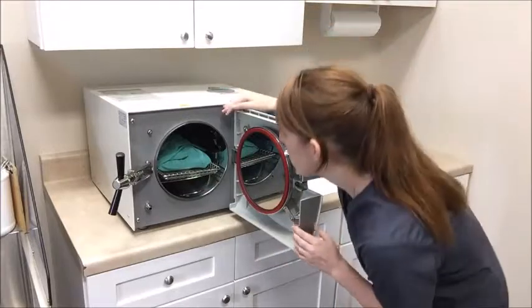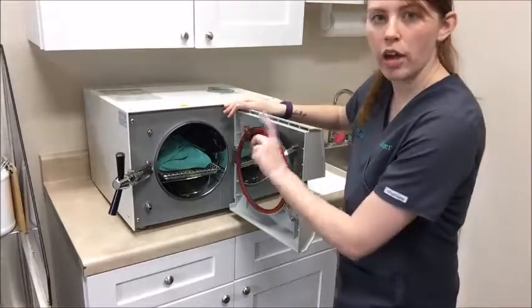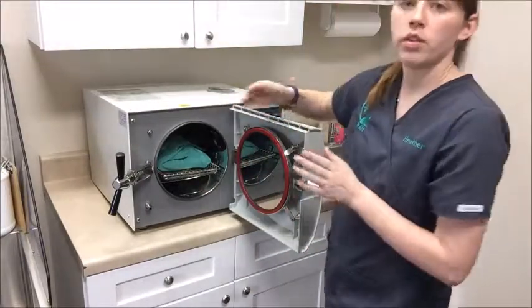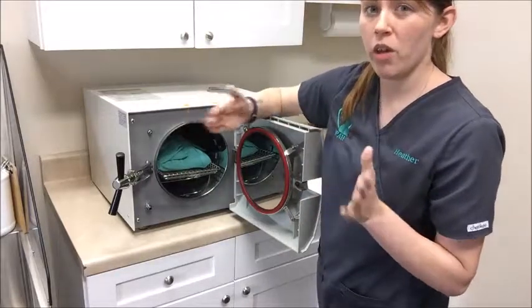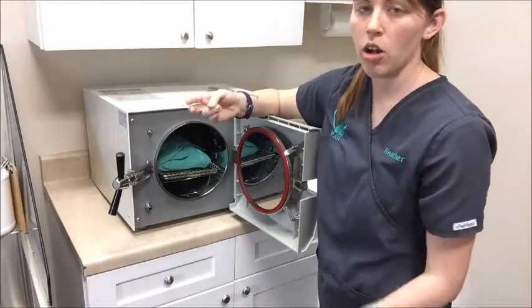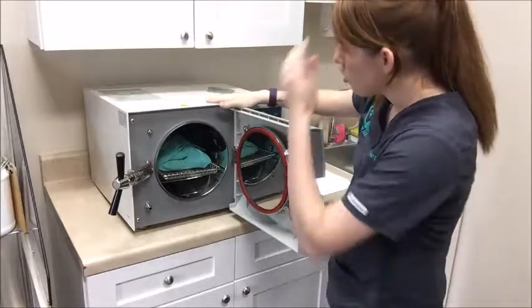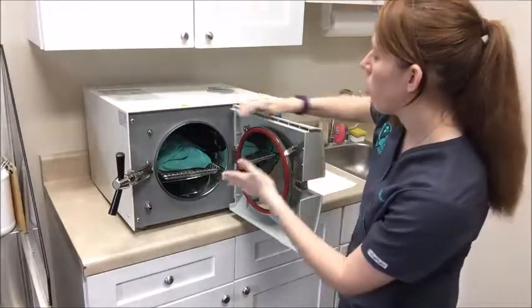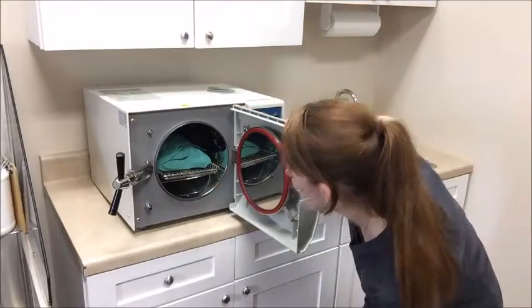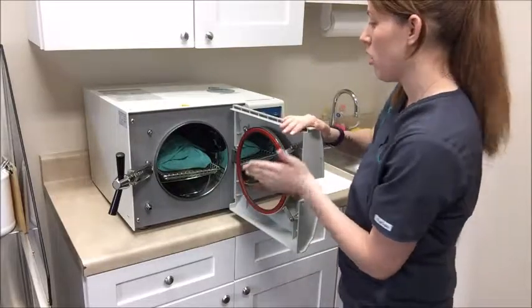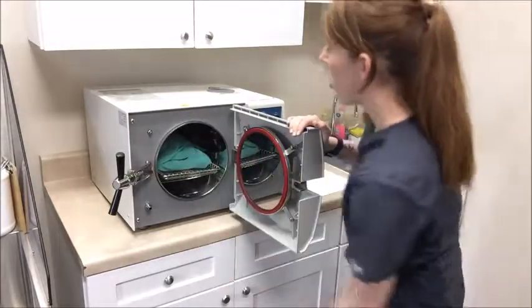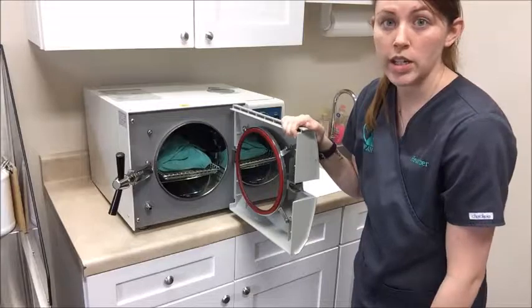So I'm going to just take a peek inside. There's about 2 inches on either side. I don't want my pack to be touching the autoclave on either side, as that can compromise the sterility of the pack. So that looks good on both sides. It's not touching anything besides the tray that it's sitting on. So once that is right in the center of the autoclave, it will get the appropriate steam to it.